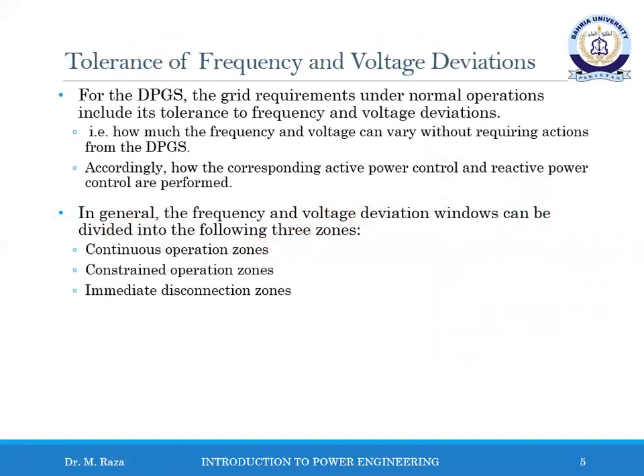For the distribution power generation system, the grid requirements under normal operation include its tolerance to frequency and voltage deviation. That is, how much the frequency and voltage can vary without requiring action from the distribution power generation system. Accordingly, how the corresponding active power control and reactive power control are performed. In general, the frequency and voltage deviation windows can be divided into the following three zones: continuous operational zone, constrained operational zone, immediate disconnection zone.